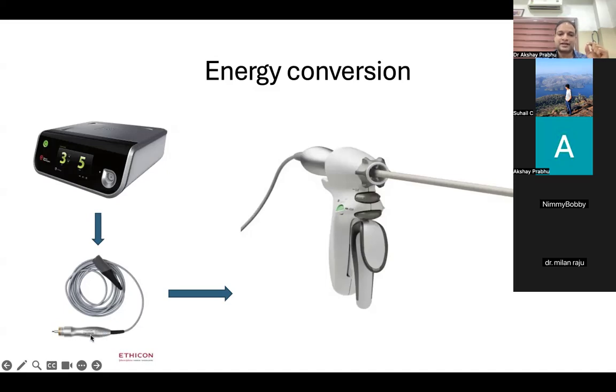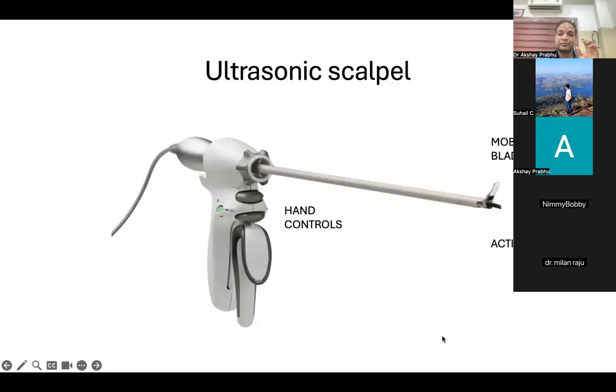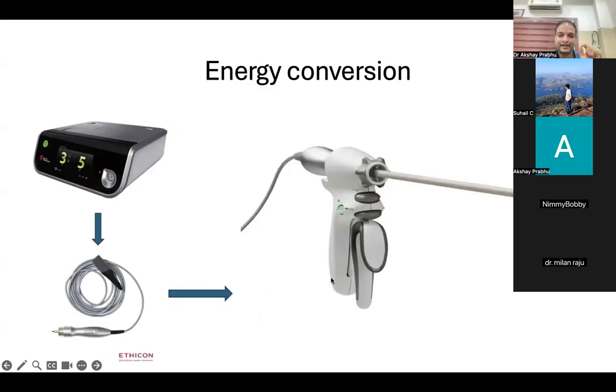This conversion happens because there are quartz crystals inside this handpiece. So electrical energy gets converted into sound energy. Ultrasonic energy is basically sound energy. We call it ultrasonic because this is converted into a frequency of 55,000 hertz. That means 55,000 vibrations happen in a single second. So this is how conversion happens from electrical energy, with the use of the handpiece, into the probe, which is what we use for coagulation and cutting. There is a vibration of the tip of the instrument to the tune of 55,000 hertz, which is equivalent to 55,000 vibrations per second. So this is how the entire energy pattern flows.